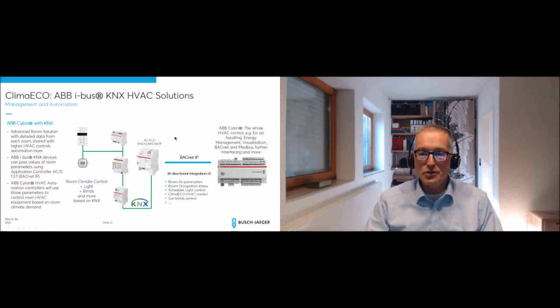So in some cases, we have to say KNX is not sufficient for HVAC, especially if we talk about air handling and other interfaces. If you talk about Modbus integration, for example, all these things are possible here. So our target is to do as much as possible, especially in the room, with KNX, also with HVAC, but of course also lighting and shutter, whatever security, but to integrate a further system if needed, depending on project and customer, with this BACnet IP gateway application controller, to have more functions with other components.